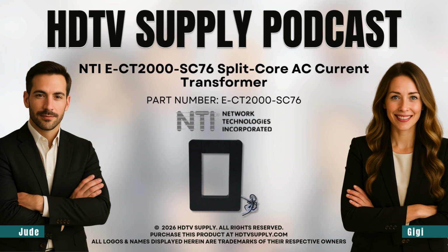But accuracy is only half of it. The other, more important half, is safety—the 3 kV galvanic isolation. This is absolutely non-negotiable. It's an electrical firewall. You have this sensor sitting on a line with immense power, and there's always a risk a surge or fault could cross over from that high power side to the low power monitoring side, frying your expensive monitoring gear, or worse, injuring a person. The 3 kV isolation creates a physical, non-conductive barrier—it lets the data pass through but ensures dangerous voltage cannot. It protects the equipment and it protects people.